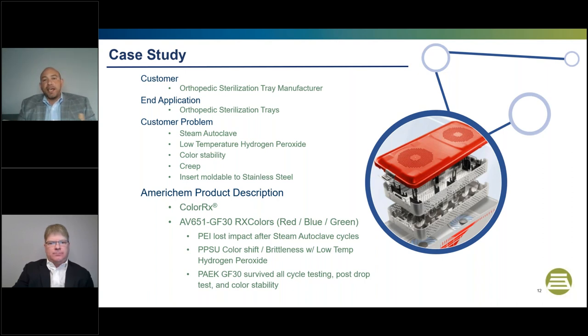So in this case, Ultem lost impact with the steam autoclave cycle. Radel had a color shift and embrittlement problems with the low temperature hydrogen peroxide. The PEEK or PAEK, Avaspire, which is in the PEEK family, survived both sterilization processes. So now we have the polymer set. You can see the part in red there on top.